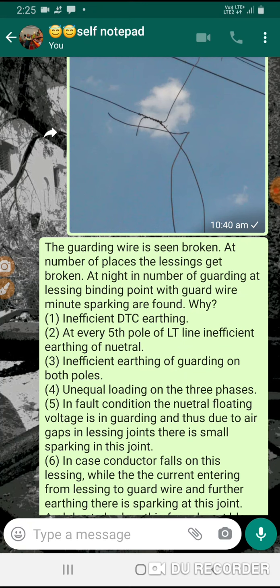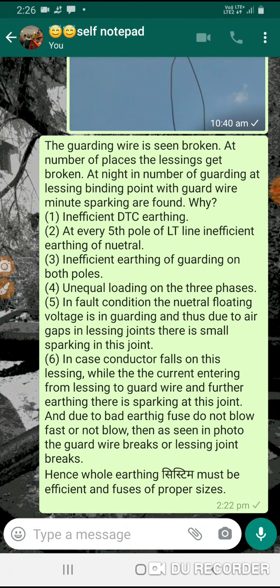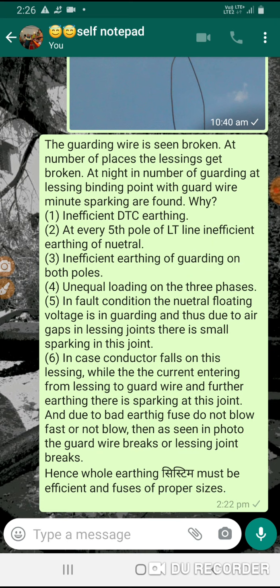These sparkings are there due to: 1. Inefficient DTC earthing. 2. At every pole of the LT line, inefficient earthing of the neutral conductor. 3. Inefficient earthing of the guarding on both poles. 4. Unequal loading on the three phases, that is, all the three phases of the DTC are not equally loaded. 5. In fault condition, neutral floating voltage is in the guarding, and thus due to air gaps in lacing points, there is a small sparking in the joint.